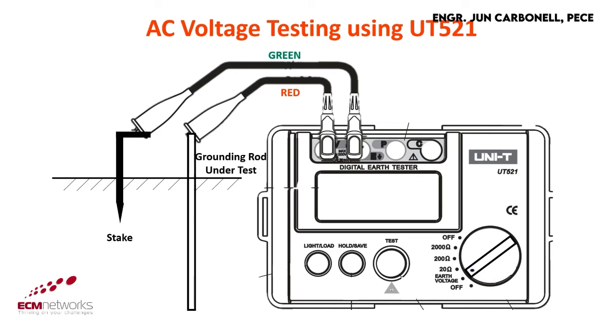Then set the knob from off to earth voltage. Ideal voltage is 0 volts up to 10 volts AC. If voltage is more than 10 volts AC, please check if the ground rod is disconnected from the grounding system.